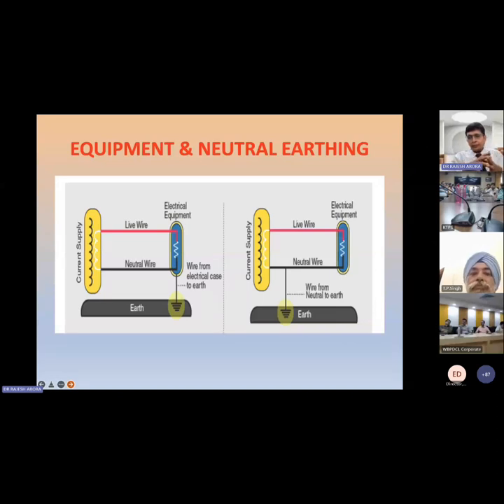Earthing and grounding. We have to understand equipment earthing. We have to understand system earthing, that is the neutral earthing. We have to understand different types of earthing system in distribution system: TN system, TN-S system, TN-C-S system, TN-C system, TT system, IT system.